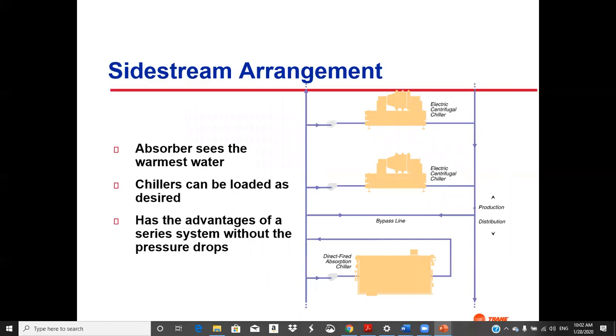And then there's this sidestream arrangement. This is pretty recommended too, because it has that same advantage. You've got your direct fired absorber here, and so this is the warm water coming back. You can pull as much as you want or all of it through this guy, maximize its production. And then if you can get it cold enough, then you can shut this off and you can just use the bypass. Well, the bypass could run either way, but you can go this way back out to the system, or you can come up and then you could put some water through here. You could bypass some, you could spread it out between these. So you get a lot of operational flexibility out of this sort of an arrangement.